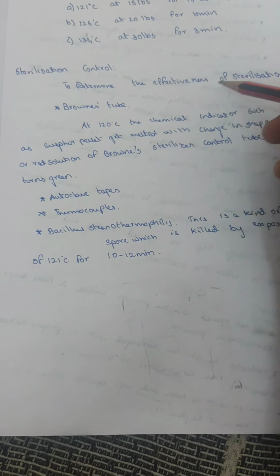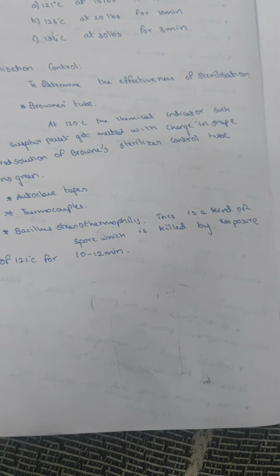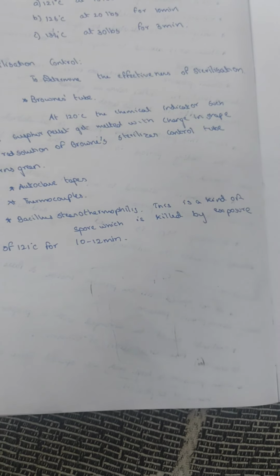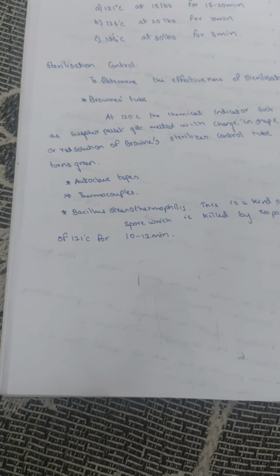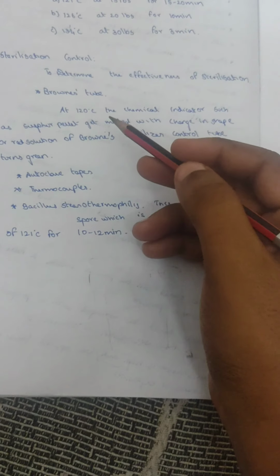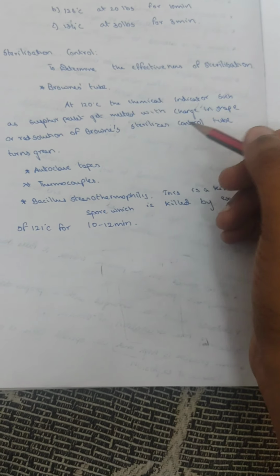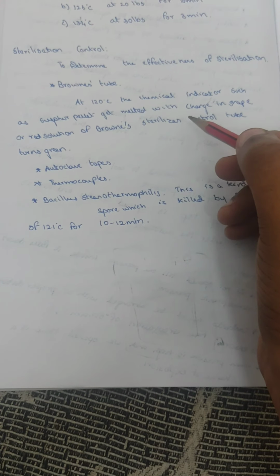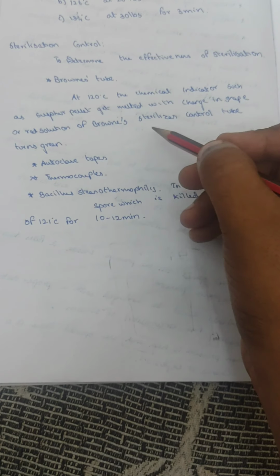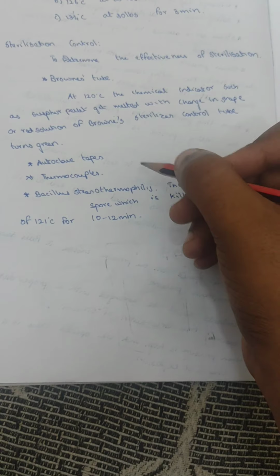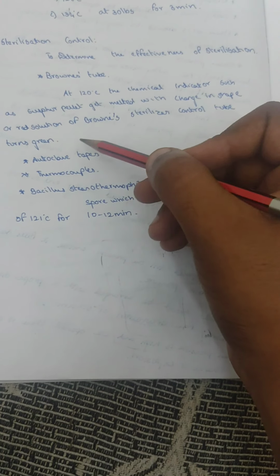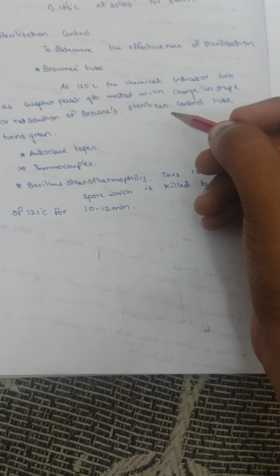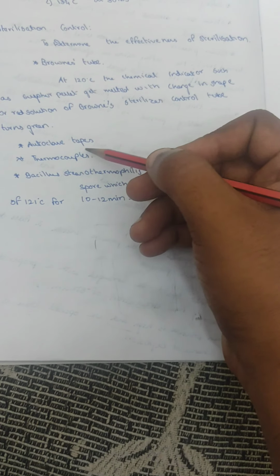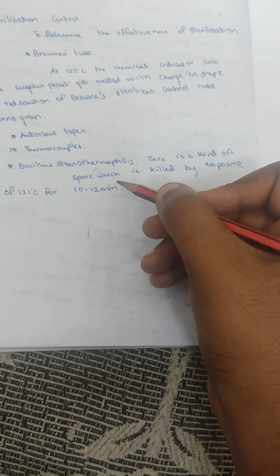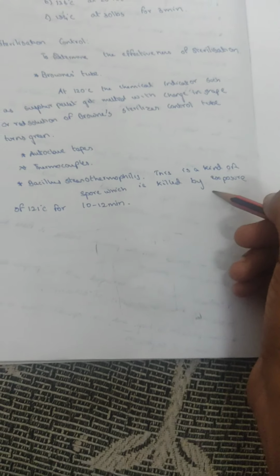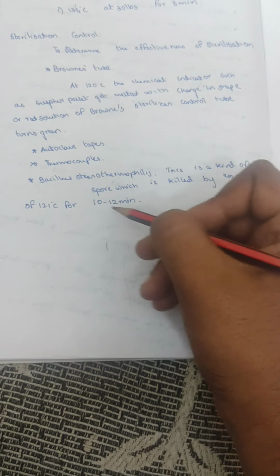Sterilization control. To determine the effectiveness of the sterilization, whether the sterilization has been done in the proper way or not, a sterilization control is kept along with the instruments in the autoclave. Browne's tube: at 120 degrees Celsius, chemical indicators such as sulfur pellets melt with a change in shape, or the red solution of a Browne's sterilizer control tube turns green. When the tube, which is red in color, turns green, proper and complete sterilization has occurred. Autoclave tapes, thermocouples, Bacillus stearothermophilus. This is a kind of spore which is killed by exposure to 121 degrees Celsius for 10 to 12 minutes.